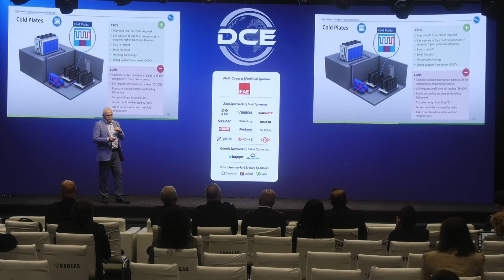And the problem is you still cannot completely eliminate space cooling. Why? Because you want to avoid condensation. If the air in the data center is too hot and humid, you reach the dew point and end up with water inside your rack, which nobody wants.